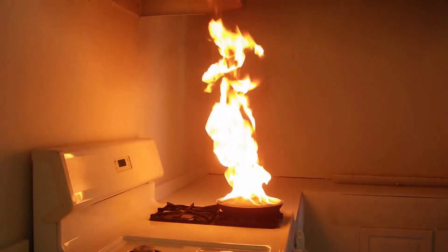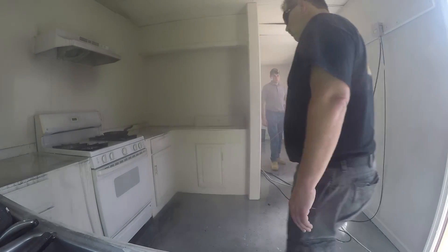It was really interesting — an infrared camera scans the room, finds the point of heat, and then focuses the water suppression at that location. That was something new I had never seen before, and it was really effective in getting to the fire quickly. In all three of the water mist tests, what was very interesting was how quickly the system responded each time. The amount of water used in each instance was very small, and upon conclusion of the test there was virtually no damage at all to the room or the contents.